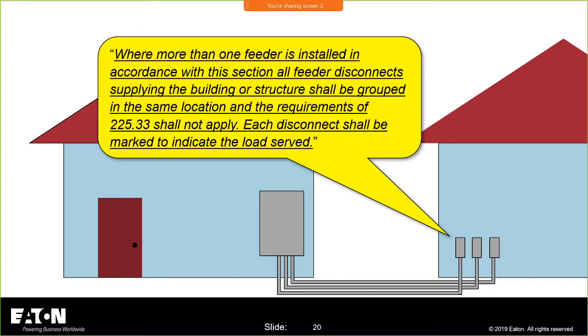But in any case, the available fault current at both of these locations is the same. When I change from a single feeder from here to that structure, that feeder is going to be a large conductor, which will have a lower impedance. My fault current at this side will be higher. When I separate into multiple disconnects and multiple feeders, I'll be reducing the wire size, which will decrease the size of the overcurrent protective device in this main equipment. And because the size of that device is lower, the available fault current and arcing current at these remote locations will still be in the instantaneous region of those breakers. So I'll have lower incident energy overall. I should have increased the safety, beyond meeting the needs of the design. And my gut tells me that I probably will address some of the safety concerns.